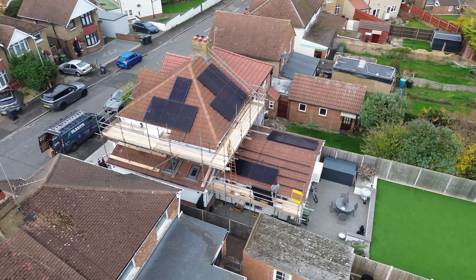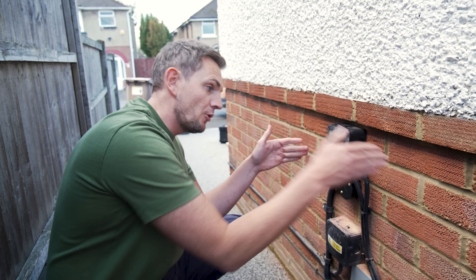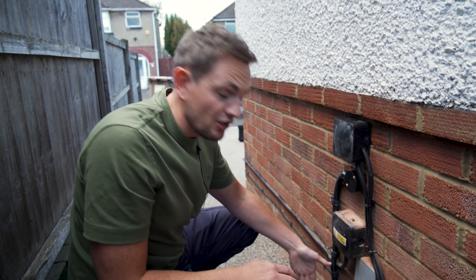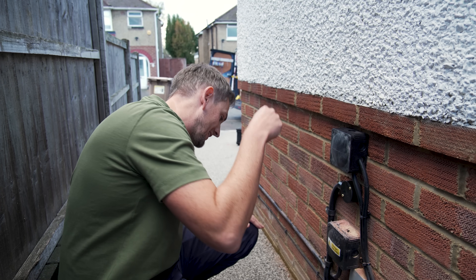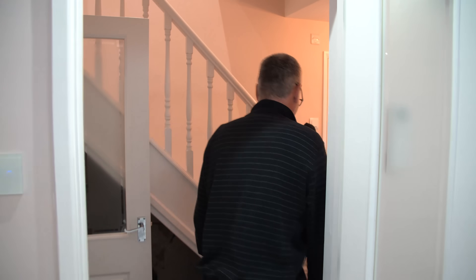Before we check the battery, let's look at how all that power gets down. Those power cables off the roof run all the way down here — this is AC current coming to this section. On the opposite side of this wall is the battery system. Something else coming out of here is the earth rod — when we go off-grid with the gateway, we lose the grid's earth, so we need our own, connected to the battery along with those power cables.